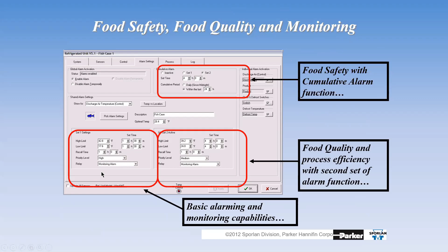All right? And this cumulative alarm looks at the difference between this and this. Now look at this. Slow me down if I'm going too fast. This is not going to trigger this particular customer if this case has to be at a bad temperature for over 1 hour and 30 minutes before it triggers the alarm. What the cumulative does is for 4 hours, it looks at the difference between 2 and 1. And even if this didn't go off for a whole 1 hour and 30 minutes, but I've had spikes here and there, and those spikes add up and they accumulate to 4 hours, I'm then going to send a food safety alarm so that you know, hey, the prime meats or the aged meat box or the sushi case, even though this alarm never triggered, I've got a cumulative alarm.